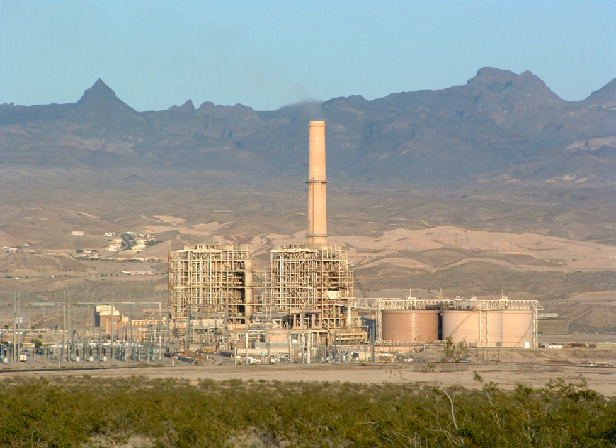Steam electric power plants use a surface condenser cooled by water circulating through tubes. The steam which was used to turn the turbine is exhausted into the condenser and is condensed as it comes in contact with the tubes full of cool circulating water. The condensed steam, commonly referred to as condensate, is withdrawn from the bottom of the condenser. The adjacent image is a diagram of a typical surface condenser. For best efficiency, the temperature in the condenser must be kept as low as practical in order to achieve the lowest possible pressure in the condensing steam. Since the condenser temperature can almost always be kept significantly below 100 degrees Celsius where the vapor pressure of water is much less than atmospheric pressure, the condenser generally works under vacuum. Thus leaks of non-condensable air into the closed loop must be prevented.